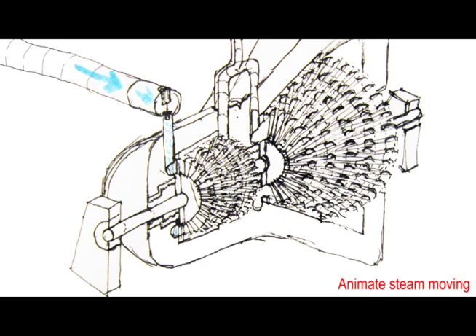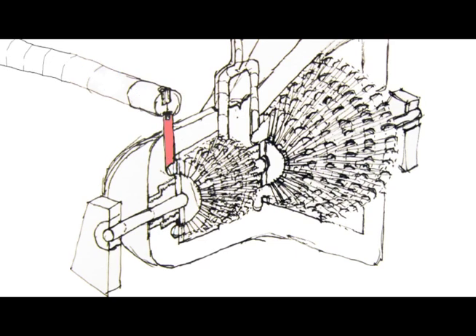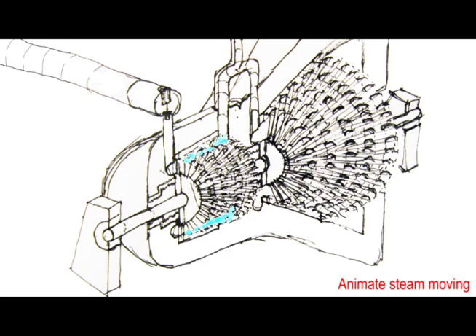Steam enters into the steam chest from the steam inlet at around 400 pounds per square inch and 700 degrees Fahrenheit. Within the steam chest are seven steam inlet valves that are regulated by governor valves. The governor valves and the steam inlet valves control how much steam is let into the turbine.